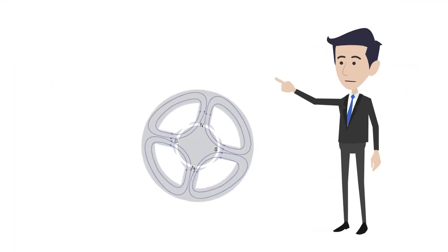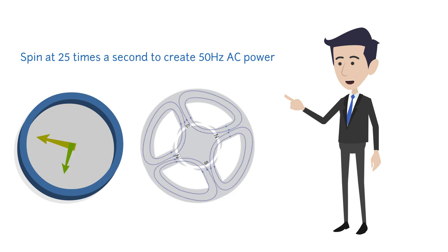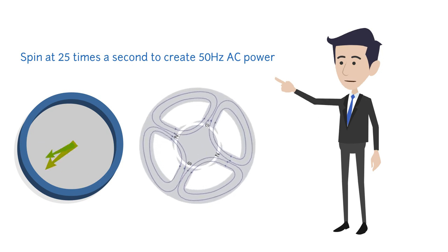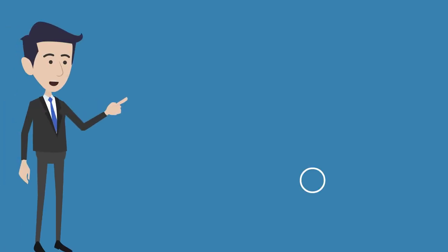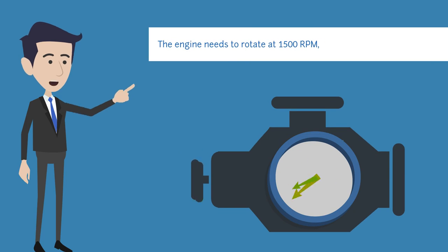A 4-pole machine therefore only needs to spin it 25 times a second to create 50 Hz AC power. With 60 seconds in a minute, the engine needs to rotate at 1500 RPM, or 1800 RPM for 60 Hz.